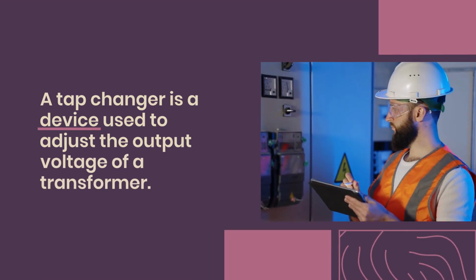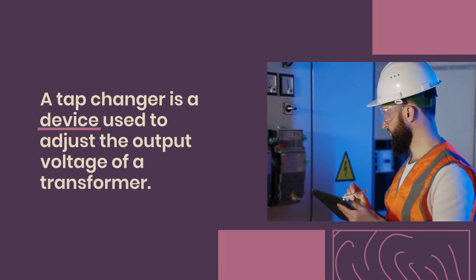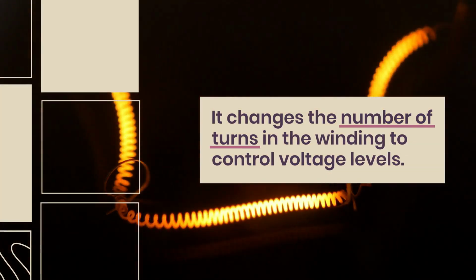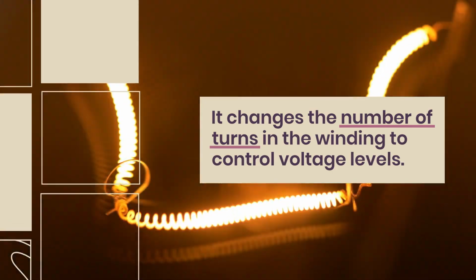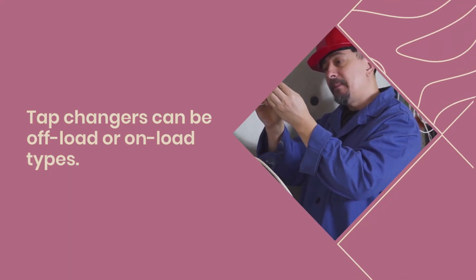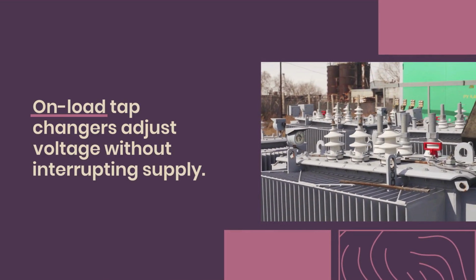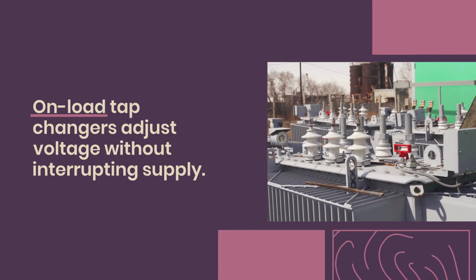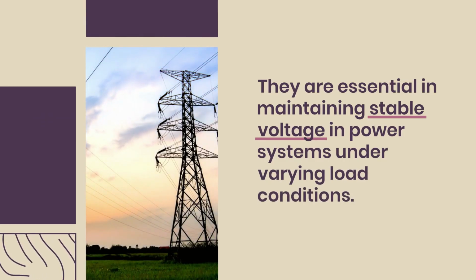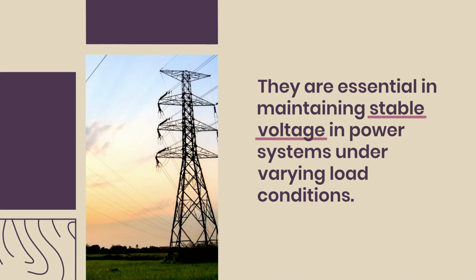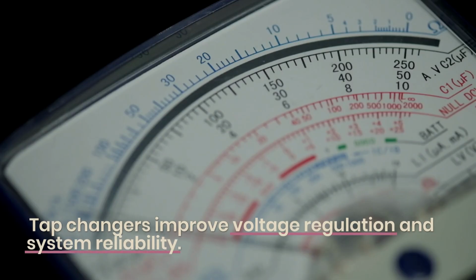A tap changer is a device used to adjust the output voltage of a transformer. It changes the number of turns in the winding to control voltage levels. Tap changers can be off-load or on-load types. On-load tap changers adjust voltage without interrupting supply. They are essential in maintaining stable voltage in power systems under varying load conditions. Tap changers improve voltage regulation and system reliability.